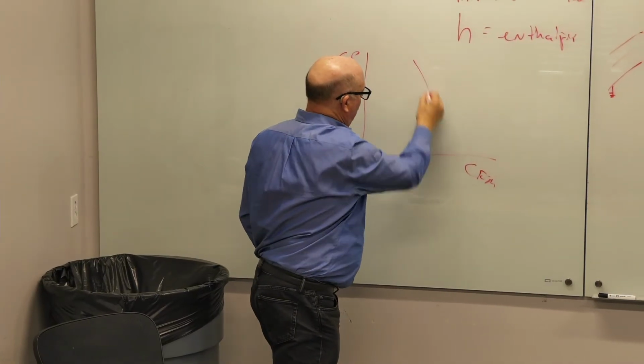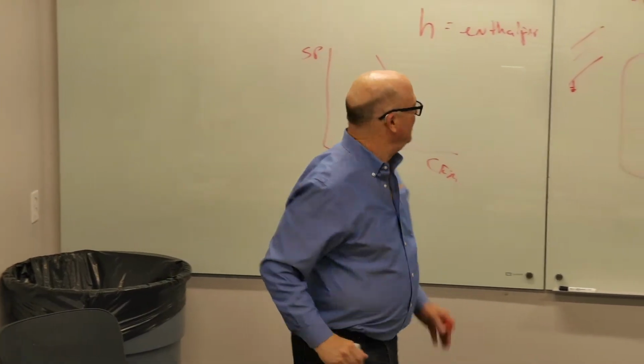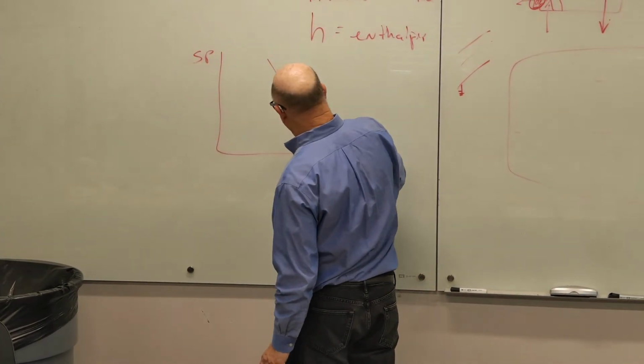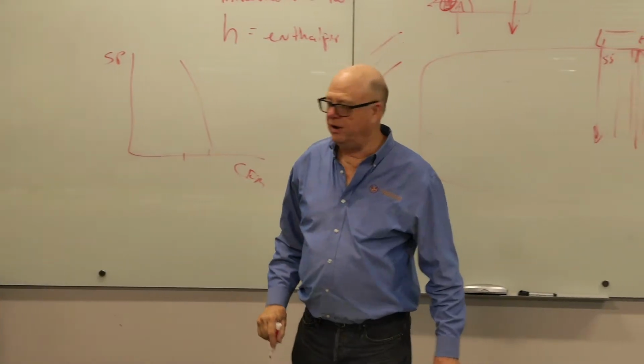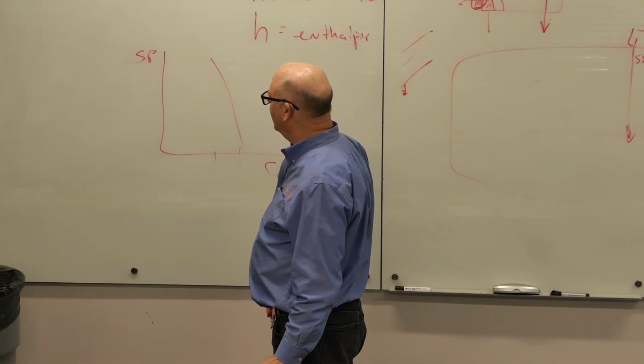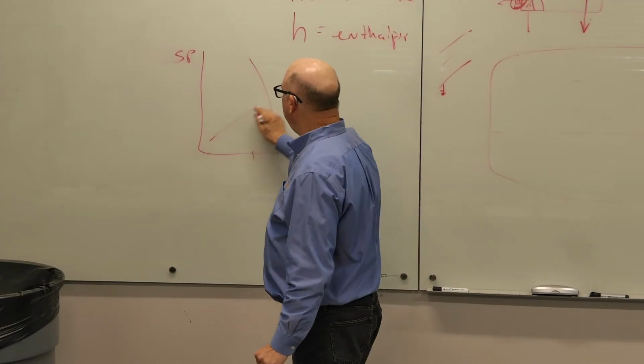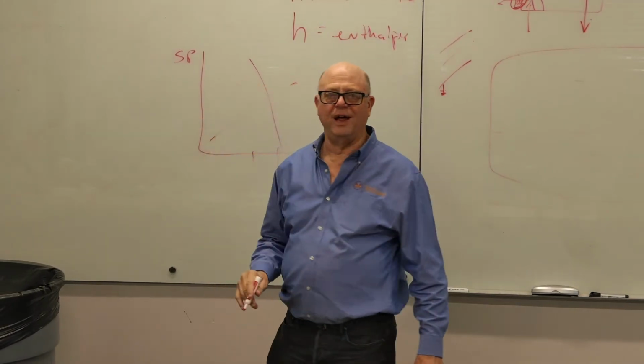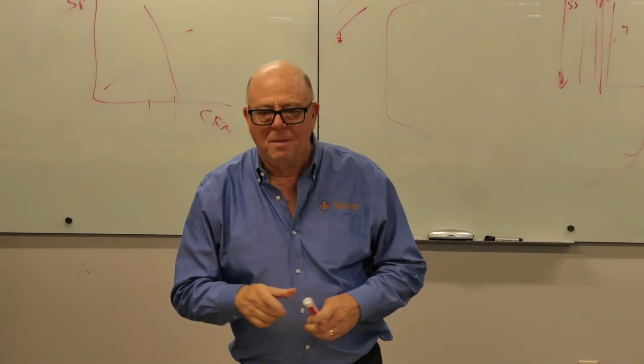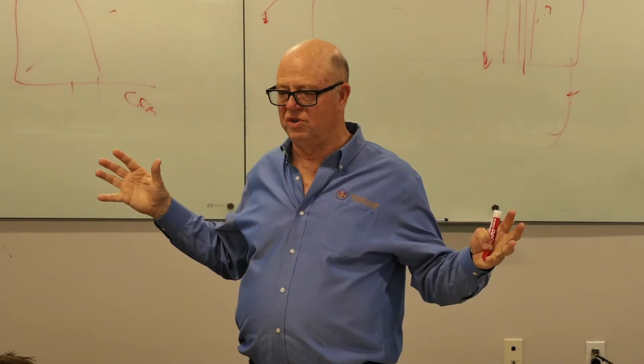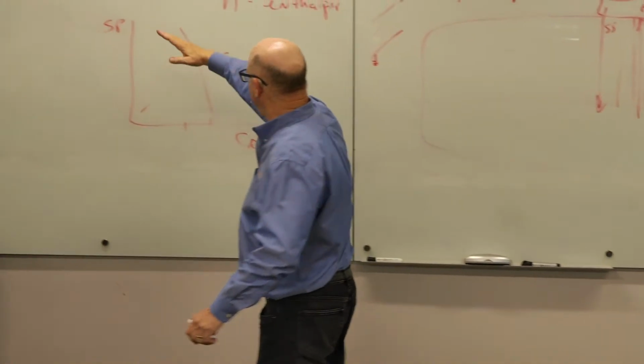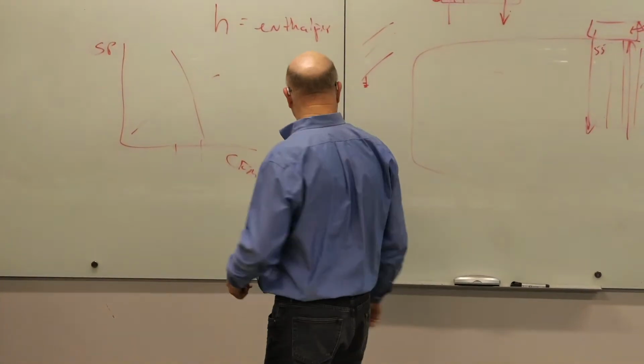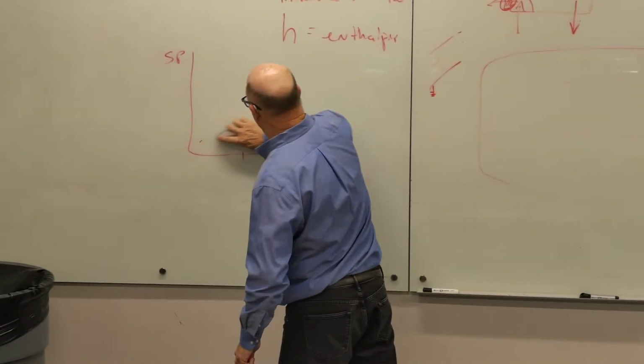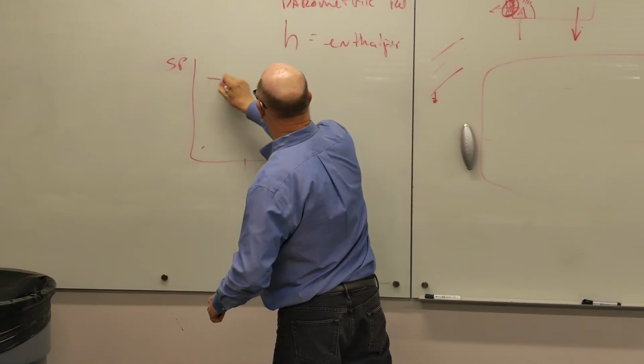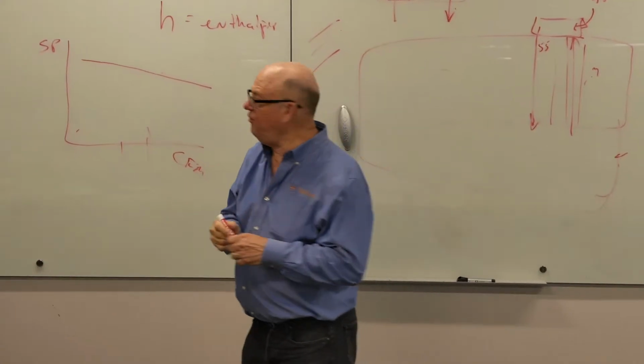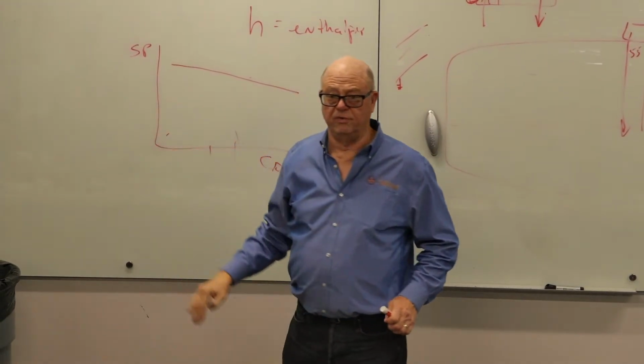So it's like this. And a small difference in airflow equates to that. Now, did I do that backwards? It's close enough. They get the point. I think maybe I got to look at it. My brain just went dead. But a small difference in static makes a huge difference in air delivery with a prop fan. Yeah, so I know that first one's wrong, because it's huge differences in, what it is. It's almost flat. That's what it was, not vertical. It looks more like this. And a small difference in static is a huge difference in air delivery.